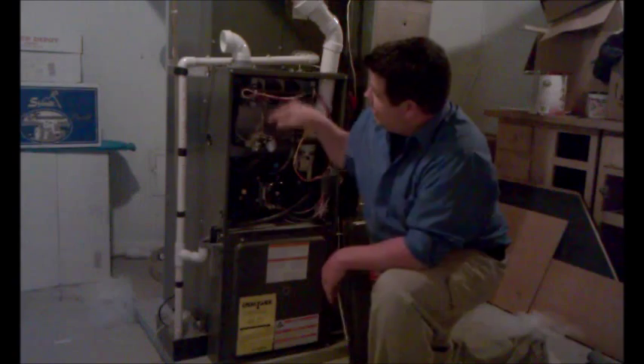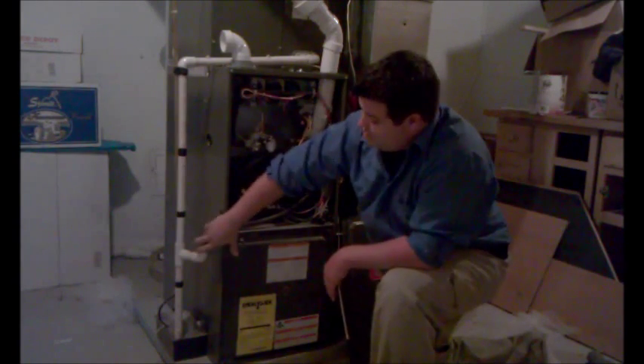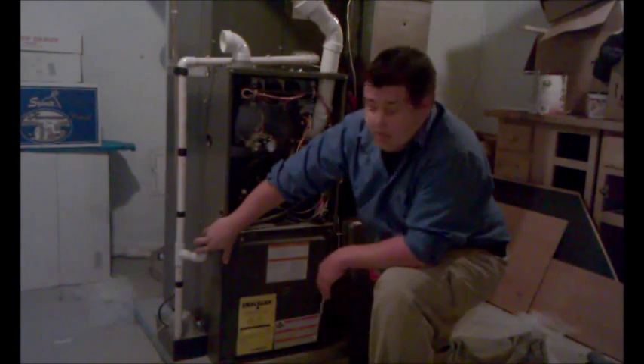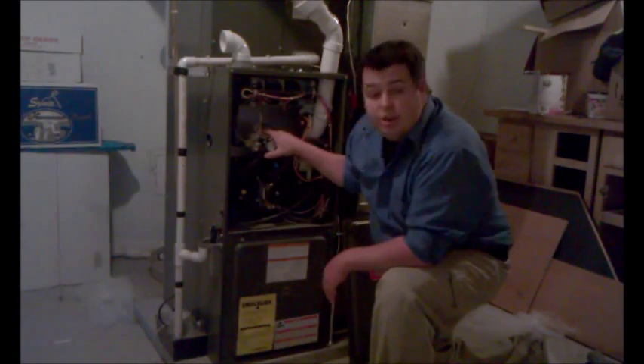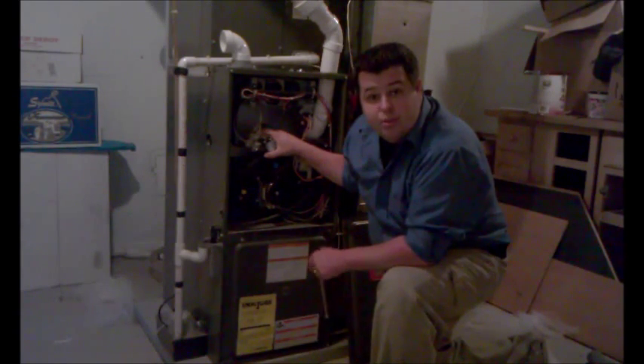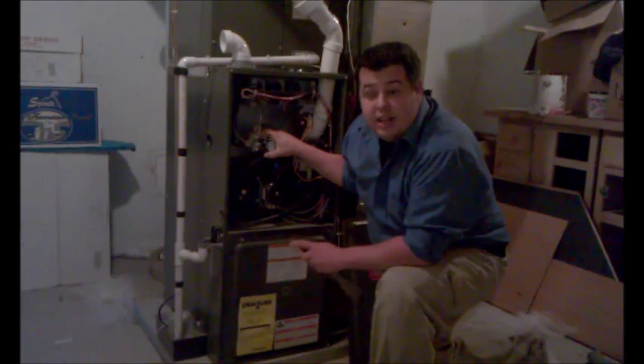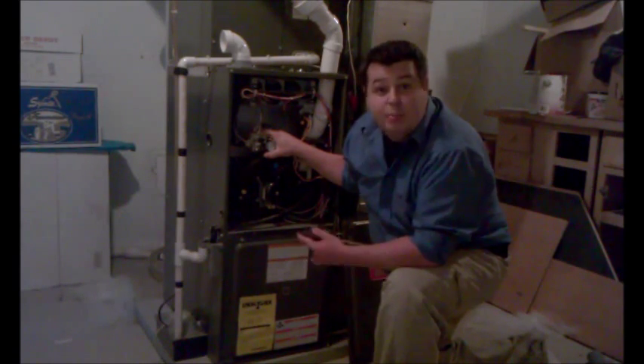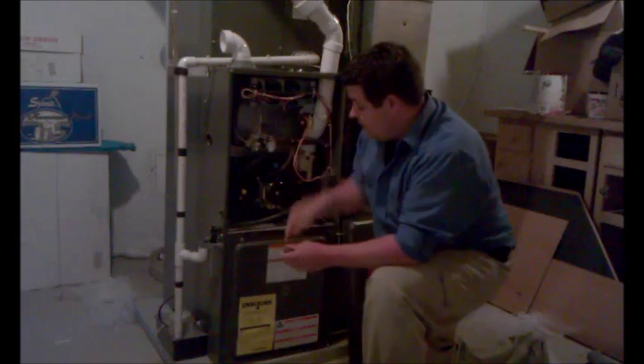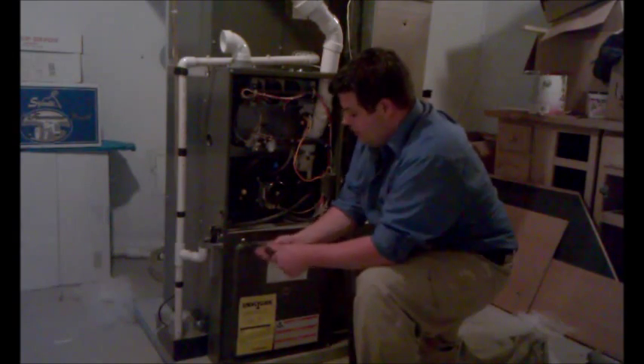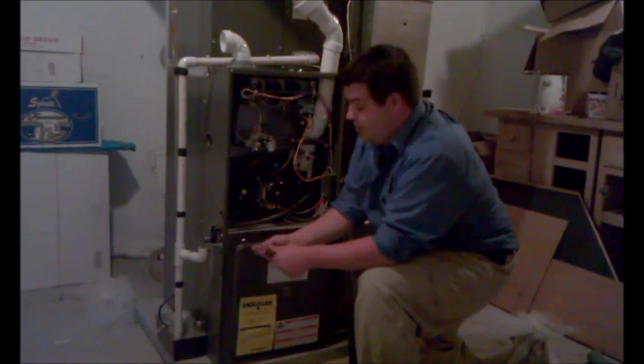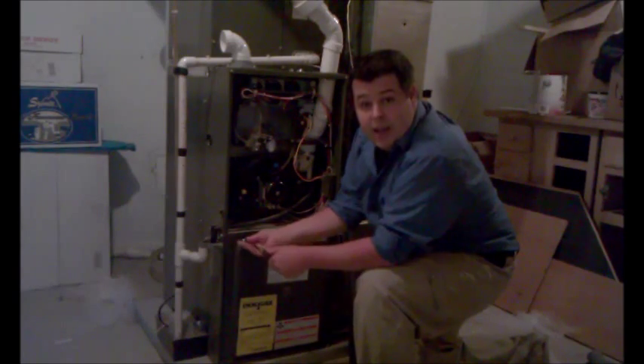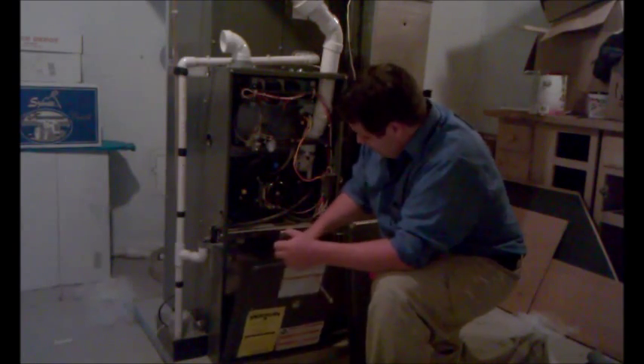The other thing we're doing is checking this drain pipe here, making sure it's draining properly. We're checking the gas valve. We're adjusting the gas pressure to make sure you have good gas pressure and it's running efficiently. Basically, you're getting the most heat for the least amount of money. All right, then we move down in here to this bottom panel. This is where the blower is, and it's what moves all the air throughout your house. We're checking that as well.